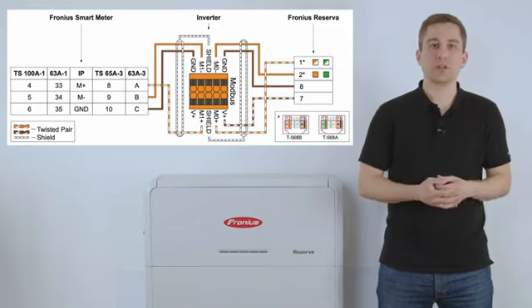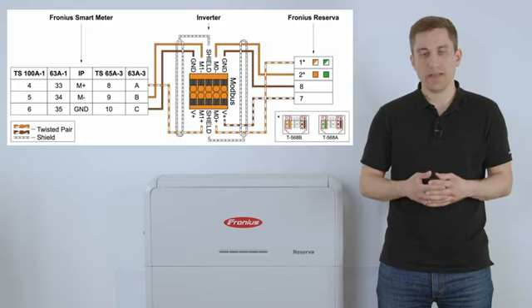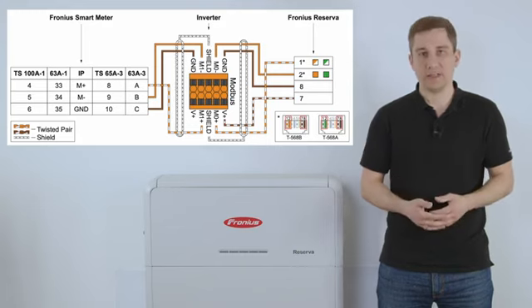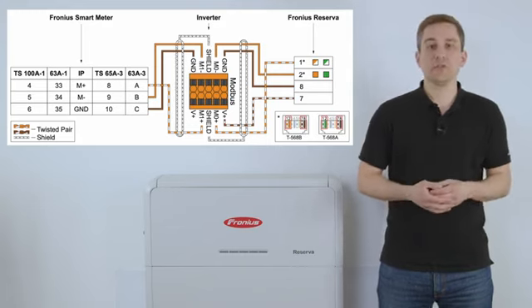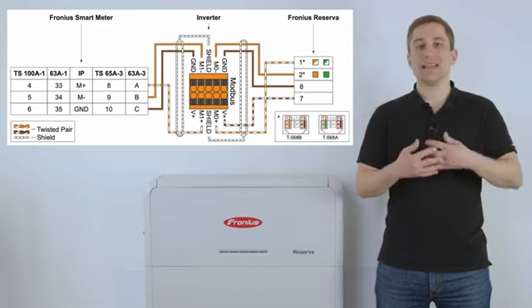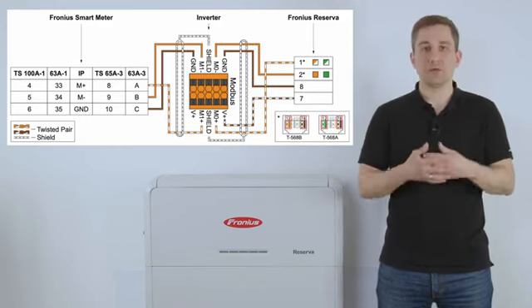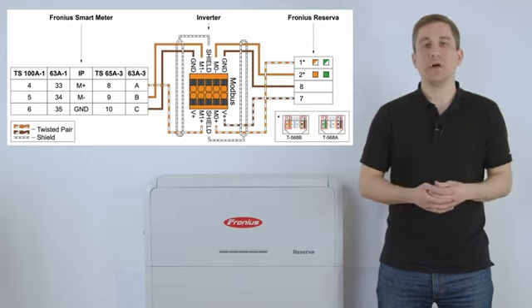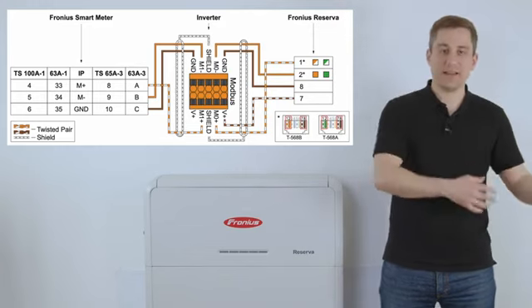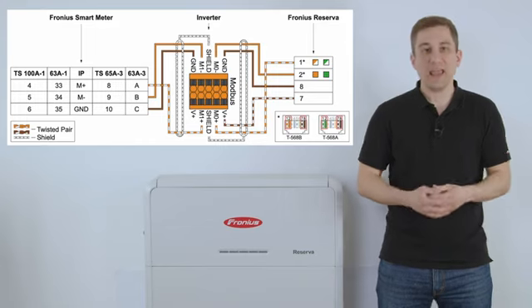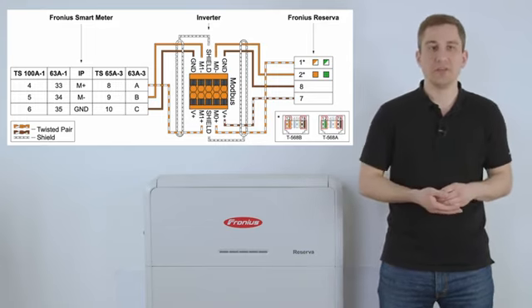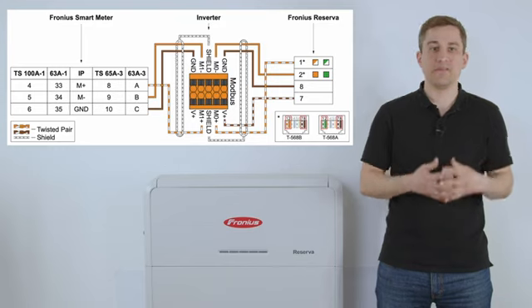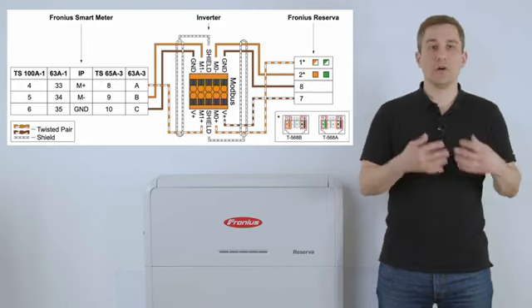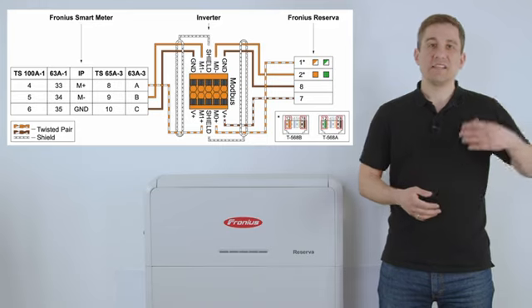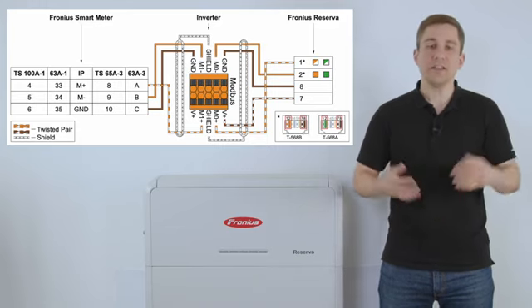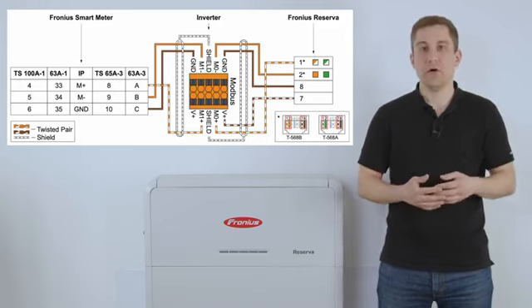Furthermore, we also want to install the Fronius smart meter at the feeding point so that the battery can be controlled correctly. Therefore, please make sure to use the M1 Plus as well as the M1 Minus contactor as well as the ground contactor, and then install it on one hand side on the Fronius inverter and on the other hand side on the Fronius smart meter. And depending on which smart meter you are using, so either the 100 amps single phase, 63 amps single phase or the smart meter IP for example, you have different contactors on the smart meter, which you can see in the schematic that is now online.